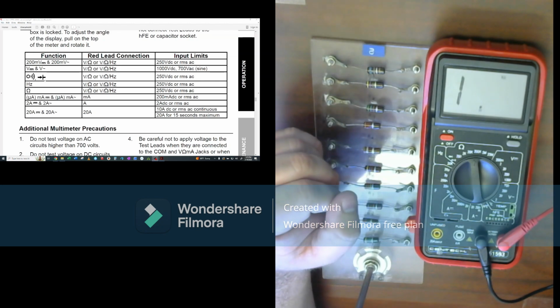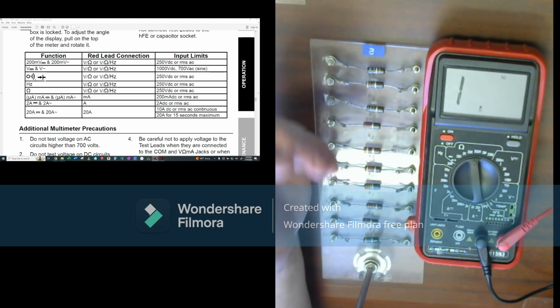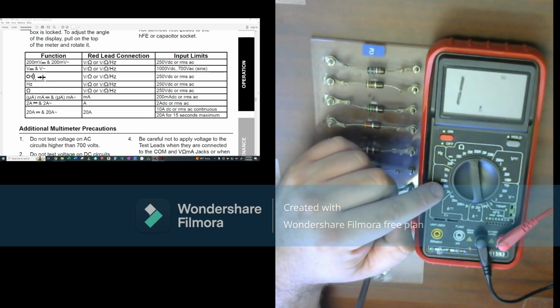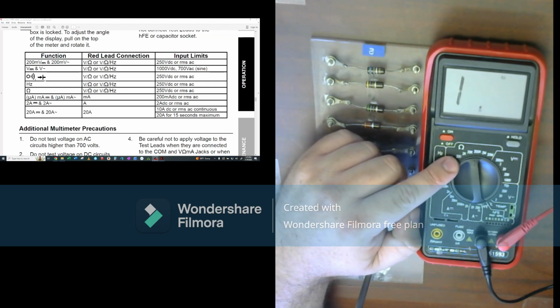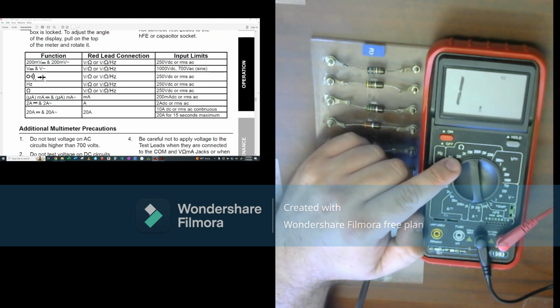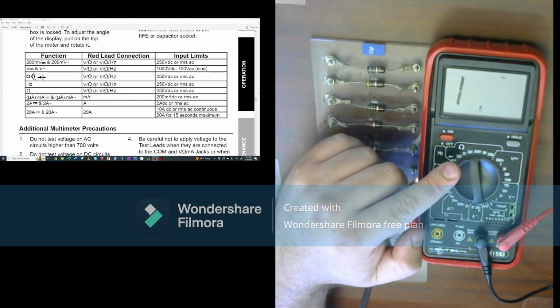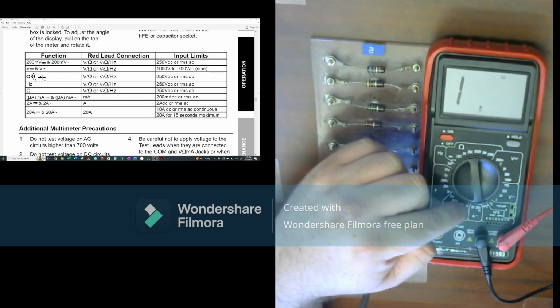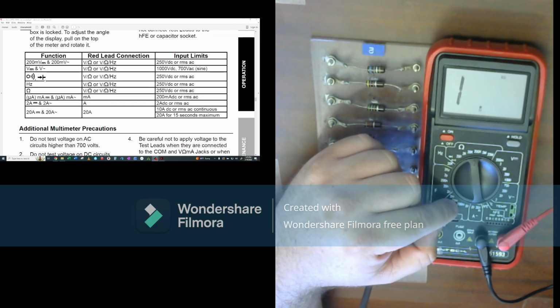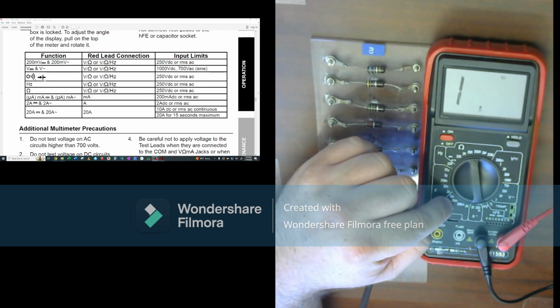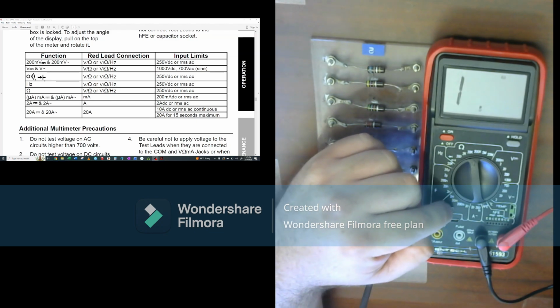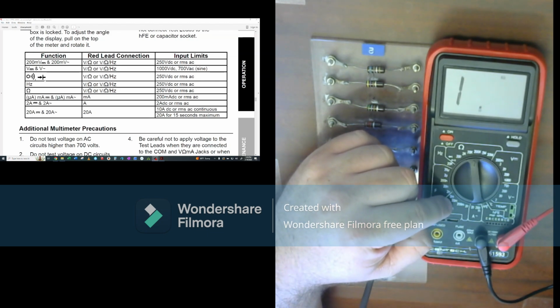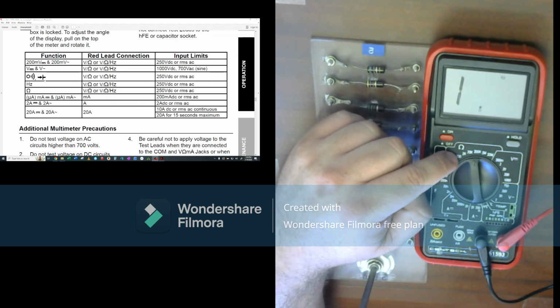The second reason we want to make sure we start high and move down is, depending on what function and setting you're on, you can actually cause problems and blow up internal parts of your DMM if it's at too low of a range. Now resistance is not that big of a deal, you can start low and go high and have a little bit of leeway. Once you get into voltages and currents, you start running into problems. If you're measuring for 20 milliamps and you're getting 40, double the amount of current it can handle, you can actually burn up components inside of it because it's not designed to handle twice as much current as what you're putting through it.